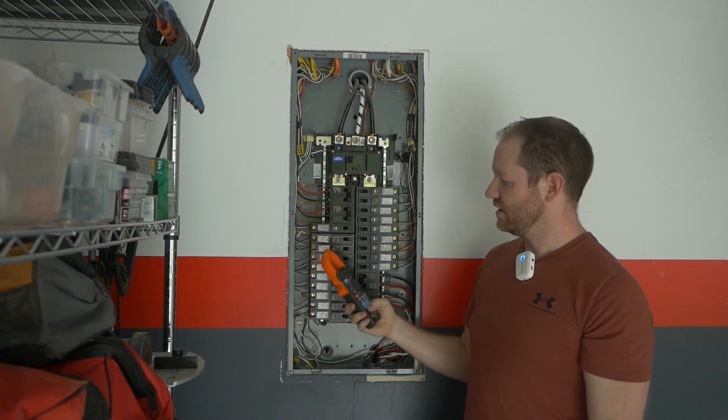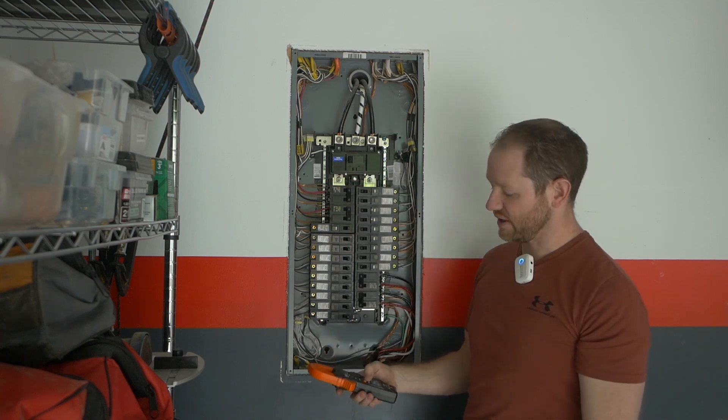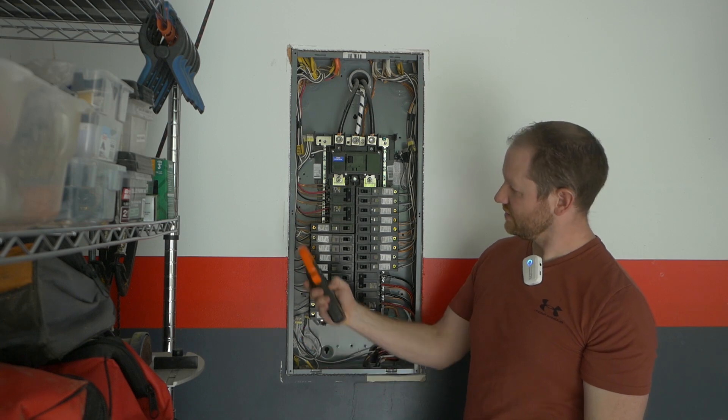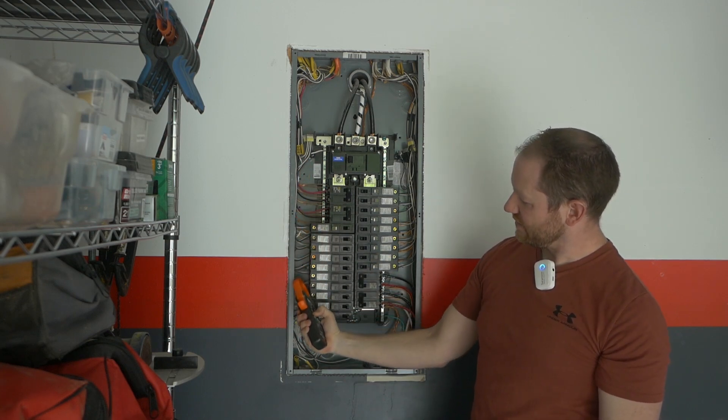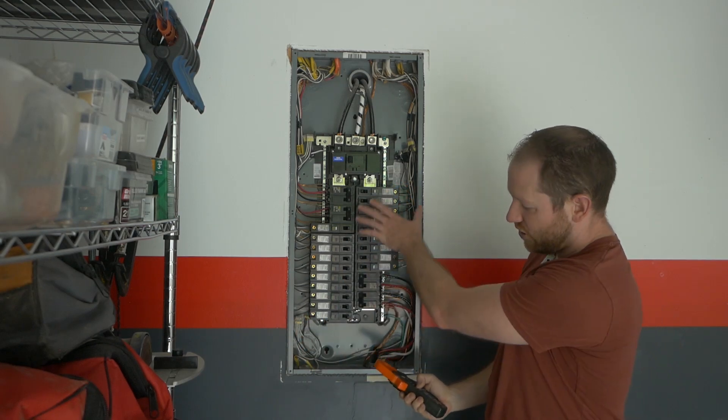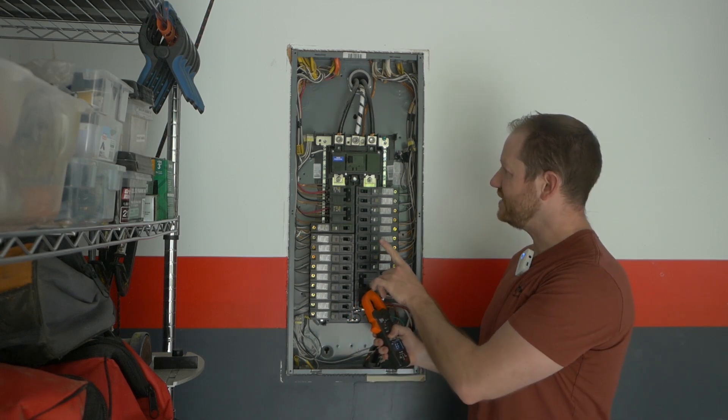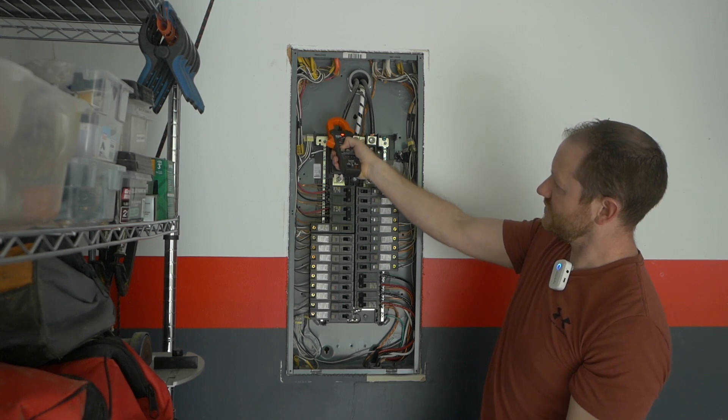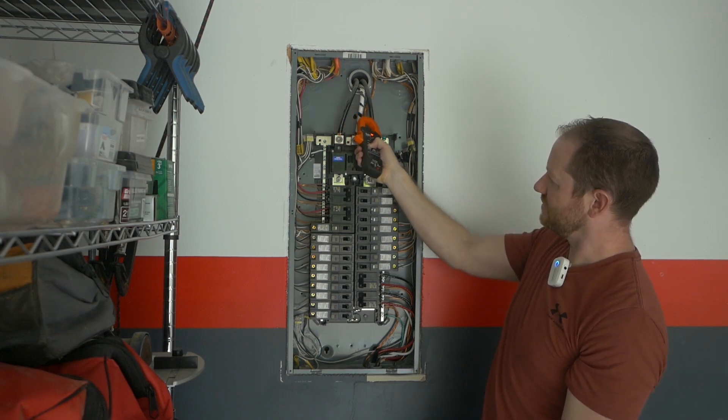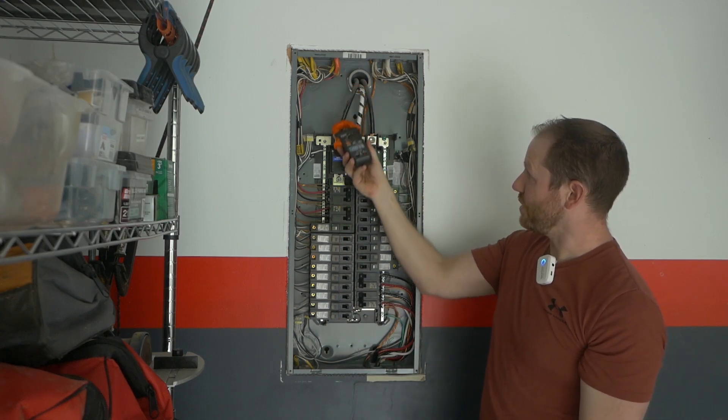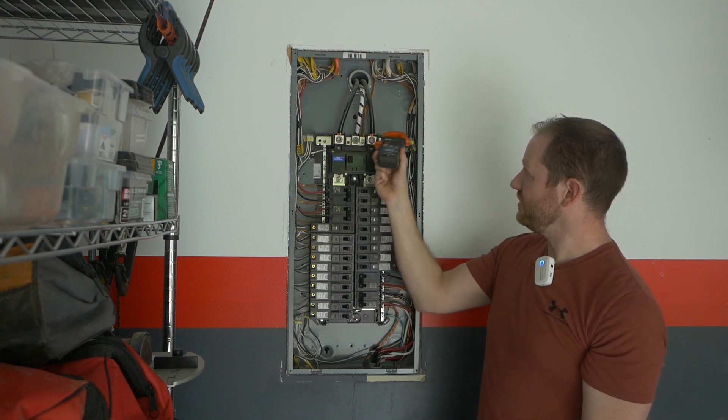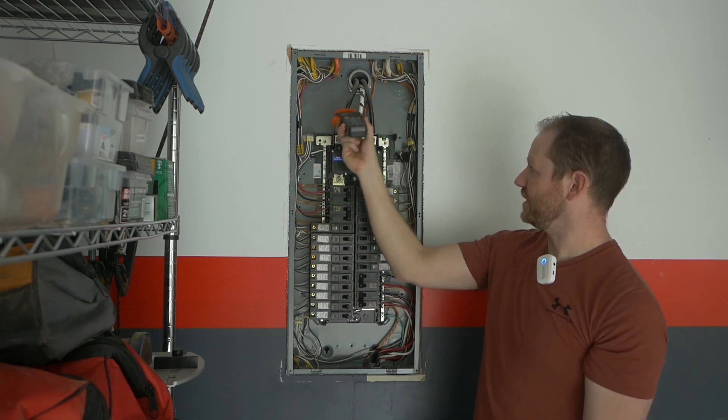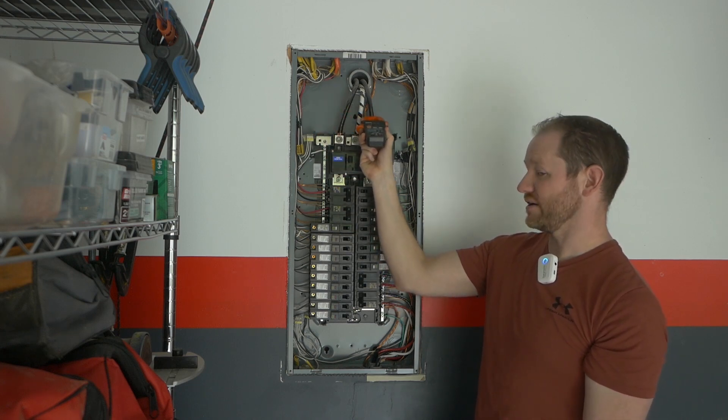As you just saw, I flipped off the main breaker here, so that's going to de-energize everything below the breaker. If we turn on our non-contact voltage detection, we can just kind of run through here and there's no alarms going off, so we know that all this is indeed de-energized. But what happens if I go above the main breaker? The power coming in from the utility is still live even though I've cut power below it. So just be very careful when you're up here because even though you've cut off the main breaker, there's still live power in this panel.